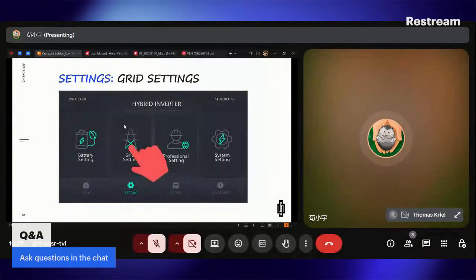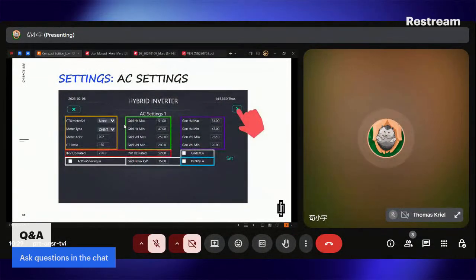Then let's go to the grid setting. So in the AC settings 1, you can select the CT and the meter types. If you are not using them, you can just select none. If you are using them, you need to select the correct meter type and the meter address and the CT ratio. These are the specifications on the CT or meter itself, so you need to check it and input that here.